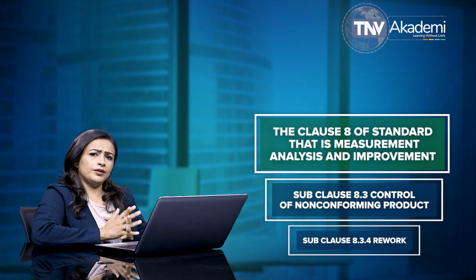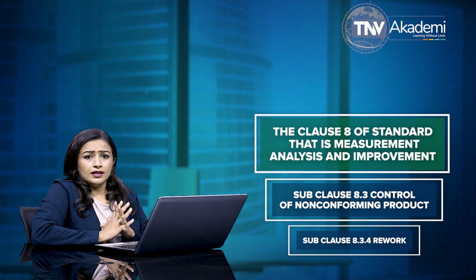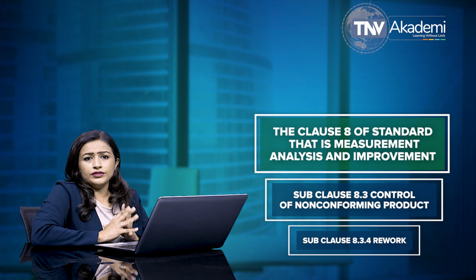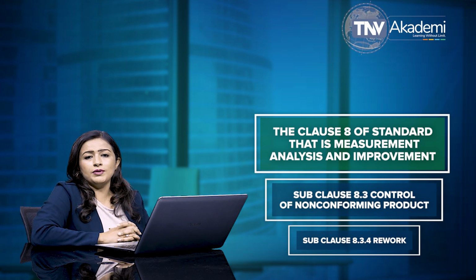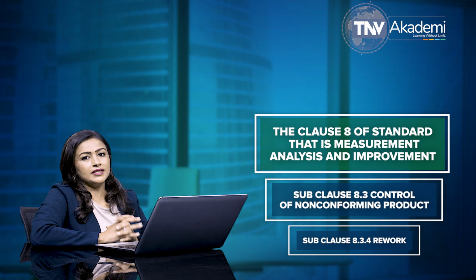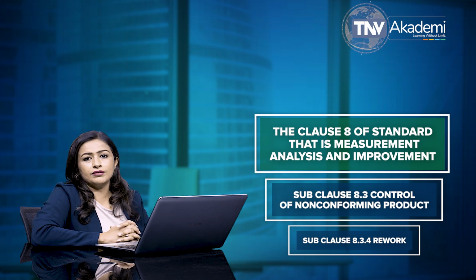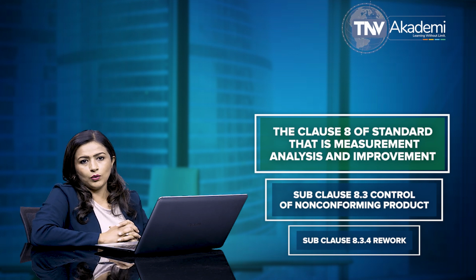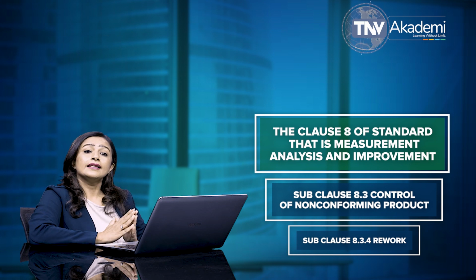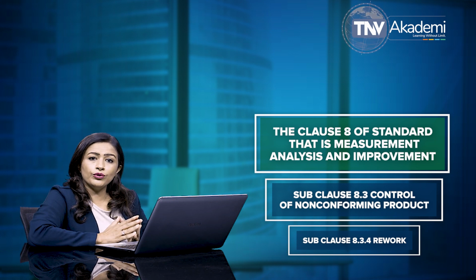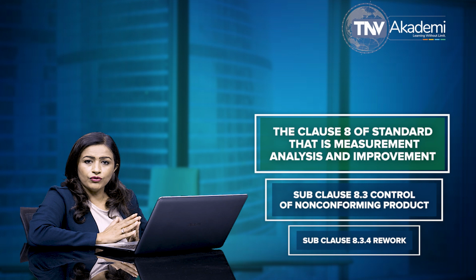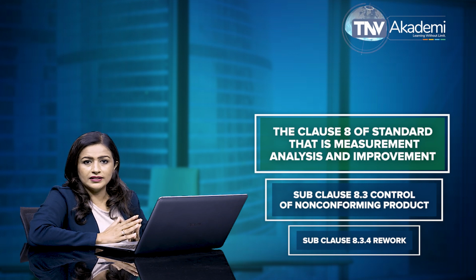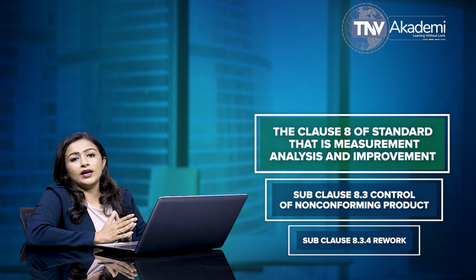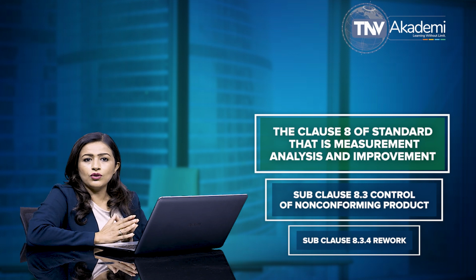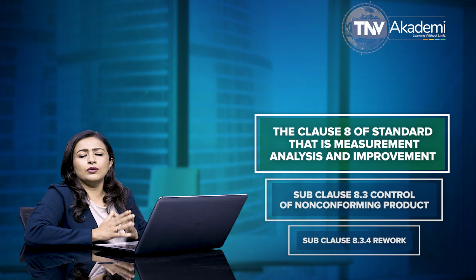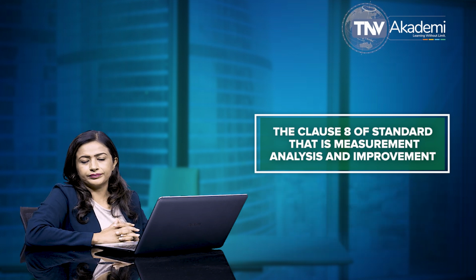Clause 8.3.4 states that after the completion of the rework, product must be verified to ensure that it meets applicable acceptance criteria and regulatory requirements. Lastly, the subclause 8.3.4 of ISO 13485 specifies that organization is required to maintain the records of rework to meet the requirements of this standard.